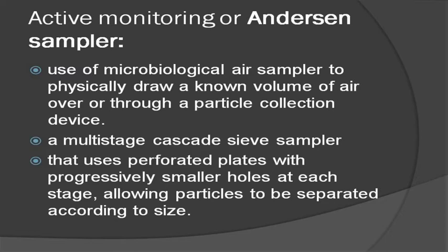One of the best known is the Andersen sampler, which is basically an impactor sampler. It is a multi-stage cascade sieve sampler that uses perforated plates with progressively smaller holes at each stage, allowing particles to be separated according to size.